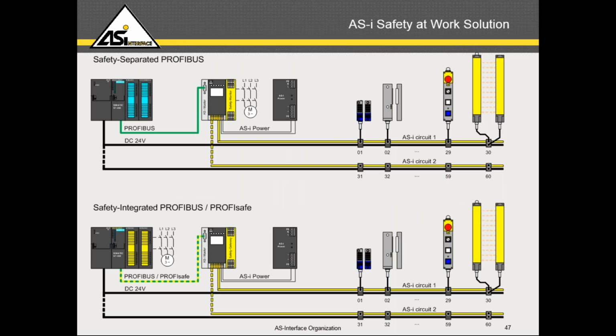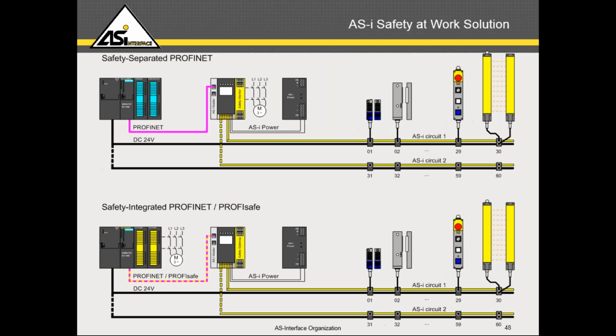If we talk about another solution in the same line, we have a safety version where the ASi master monitor is built in with monitoring and has a built-in gateway that can communicate to the higher level PLC to transfer information for each slave device, so you can see the diagnostics on the HMI. The second solution is an integrated solution with PROFIsafe, where we have an ASi safety master gateway, which allows communication directly back into the main PLC with safe communication. So now your outputs can be controlled by the main processor instead of the I/O in the field. But you can certainly add I/Os, meaning output cards, to the field, as I showed you in the earlier example.